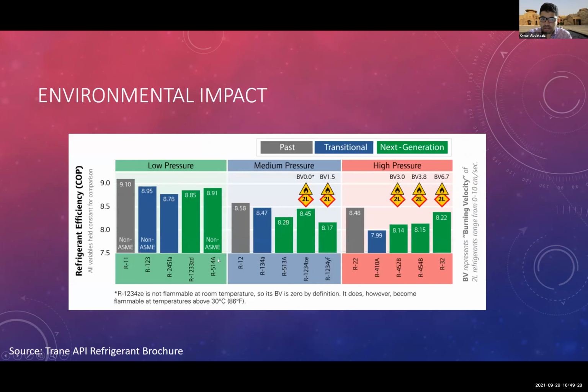We can see here the environmental impact, so the refrigerant efficiency, which is the COP. You can see that for low pressure application, when we moved from R11 to R123, we had a reduction in efficiency, and then with R245FA, even lower efficiency. But for the alternatives right now, like 1233ZD and 514, we can almost match that of R123. For medium pressure, if we compare with this baseline, the ZE almost matches the same COP as the baseline. However, it has a burning velocity of 0, but it is 2L, and you can see that 513A has slightly lower COP. It can be matched using some engineering, and it is non-flammable. For high pressure application, again, you can see that most of the alternatives have higher efficiency than the baseline.